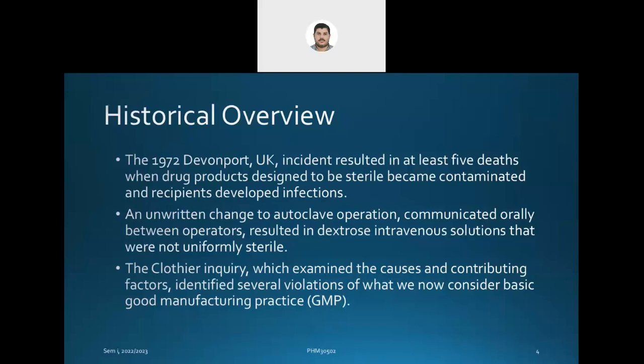Okay, so what was the cause? There was an unwritten change to the autoclave operation. There are standard operating instructions for the autoclave, and they were not being followed exactly. There were some changes in the operation of the autoclave, and these changes were communicated orally between operators. No documentation. Everything looked like they followed the standard procedure, and this variation resulted in the dextrose intravenous solutions not being uniformly sterile. What's the meaning of not uniformly sterile? It means that you put a certain number of bottles in the autoclave, and not 100% of them became sterile at the end. Some are sterile and some are non-sterile.